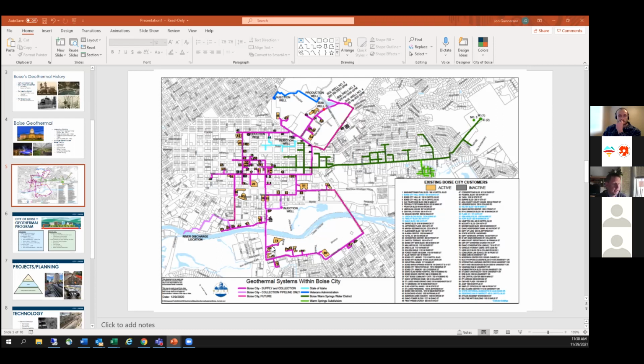I'll give an example, and it's not even a very long service. Where my cursor is here is a performing arts center on the Boise State campus, with about a 300-foot service line. Right after we extended that service line to them, they called and said every time their building calls for heat, a slug of cold water comes across their heat exchanger and actually lowers their building loop temperature. For the first 20 minutes it lowers the temperature, then for the next 20 minutes it brings it back up to where it initially called for, and they don't actually see heat coming into the building for about 45 minutes to an hour after the building calls for heat.